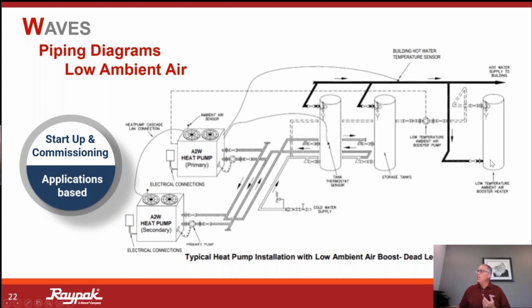So we can use this as a booster, store those BTUs, and when the ambient air temperature is such that we can no longer keep up with the demand, we'll engage this circulator and we will essentially reload our primary storage. It looks a little bit busy, but as a narrative, it's really not that far out of the bandwidth of what we normally do. Does that make sense to everybody?